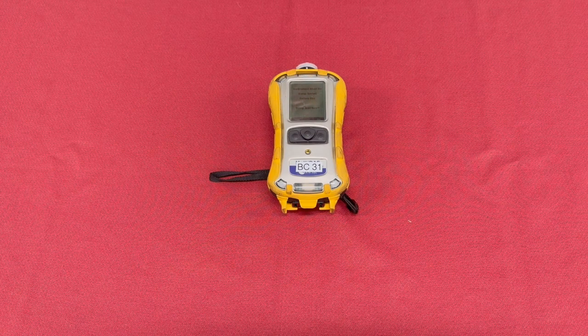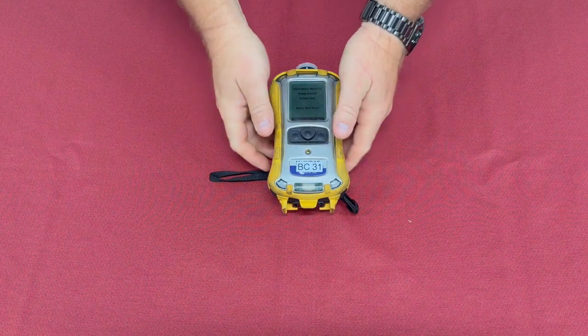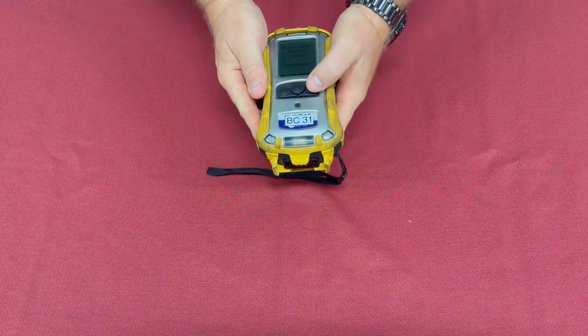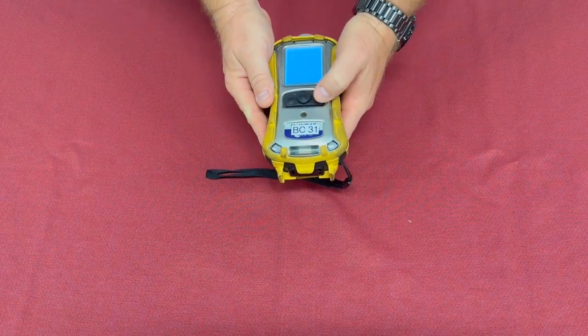This meter is calling for a bump check right now, but since I want to show you a calibration, I am going to go ahead and skip through it. If this shows up on scene, you don't have to stop and do it. You can actually go ahead and go through it. You just understand that the bump check is trying to figure out if the sensors are all working properly. And I'll talk more about the difference between a calibration and a bump as we're waiting for some of this calibration to take place. All right, I'm going to skip it so we can move on.